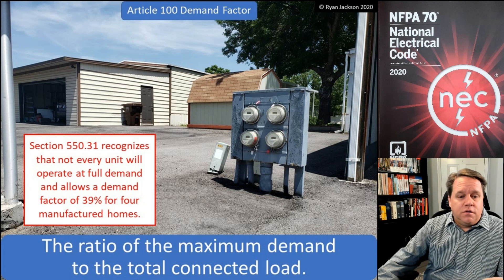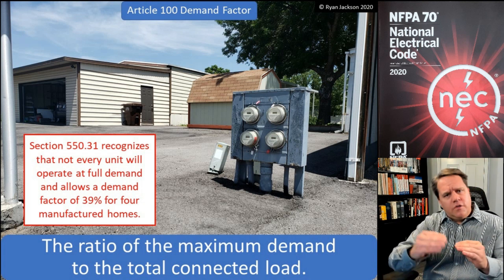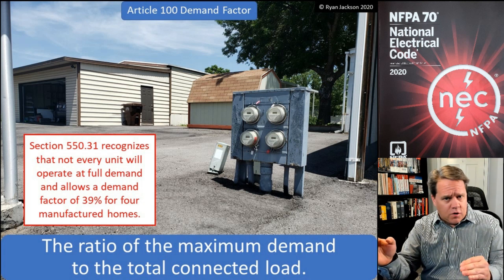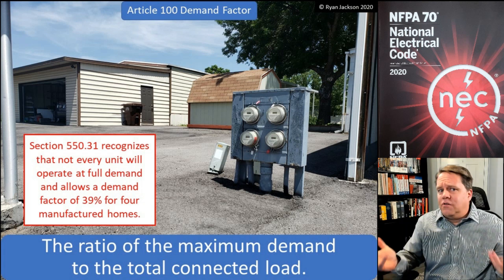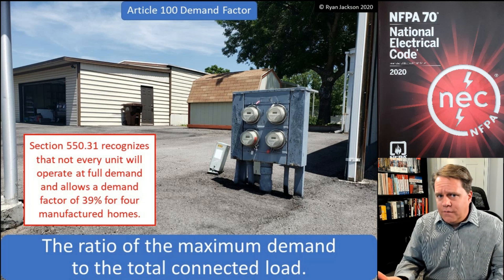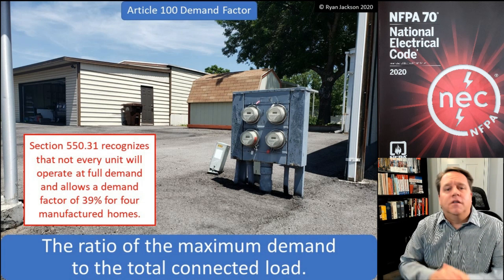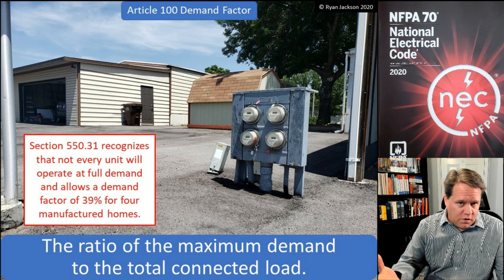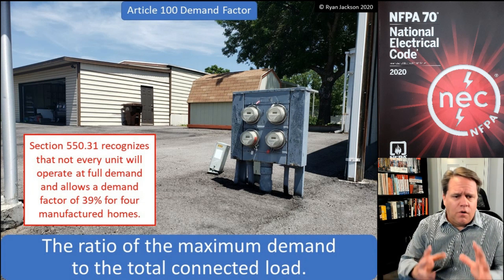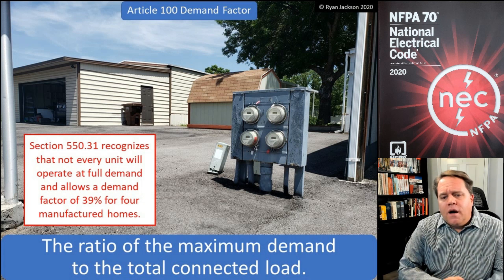Section 550.31 allows a demand factor of 39% for four manufactured homes. Of course, the more manufactured homes you have, the lower that number is going to get. Not all four units are running full bore at the same time, so we apply a demand factor and size it not at 400 amps but at something lower. That's what a demand factor is — the ratio of the maximum demand to the total connected load.